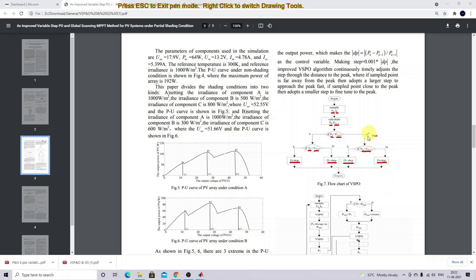For variable step calculation, you have to consider the absolute value of the power difference between the current instant and previous instant - that means the absolute difference between P(k) and P(k-1). Based upon this power difference between current and previous instances, we vary the step. This is the logic of the Variable Step P&O algorithm.